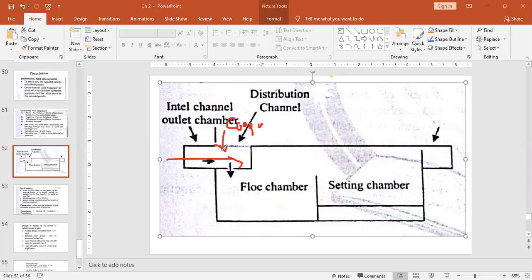Okay, so the water and coagulant together will be added into this tank, and here in the flocculation chamber there will be a mixer, and it will keep on mixing continuously. It will be stirring the water, so the coagulant will thoroughly mix into the water, and slowly it will be allowed to move towards the second chamber of the same tank, and that chamber can be identified as a sedimentation tank, because here we are not disturbing the water.